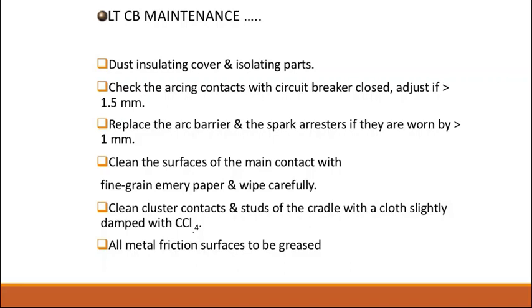And here one more thing I want to add. If the carbon deposition is more, it will always give more heating effect. For this, there is one more test conducted to identify the I square R loss or heating effect. That is nothing but the thermography test.